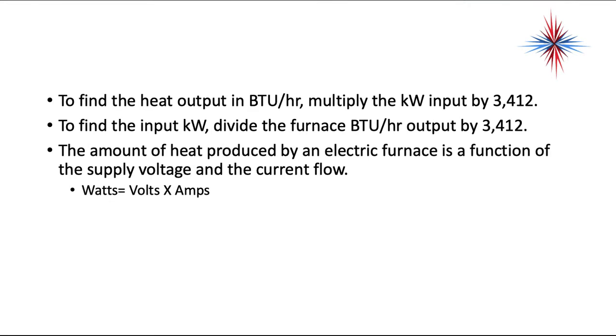To find the heat output in BTU per hour, multiply the kW input by 3,412. To find the kW, divide the furnace BTU per hour by 3,412. The amount of heat produced by an electric furnace is a function of the supply voltage and the current flow, because watts is volts times amps. So if our supply voltage is higher and our amperage is higher, our output is going to be higher.